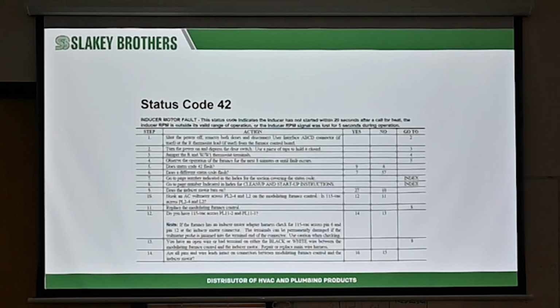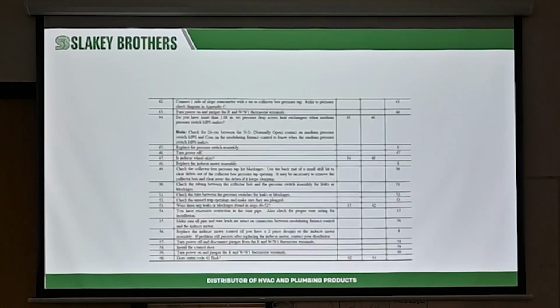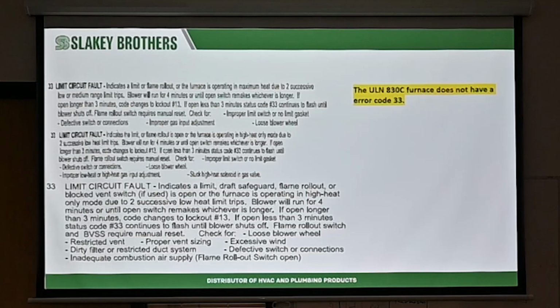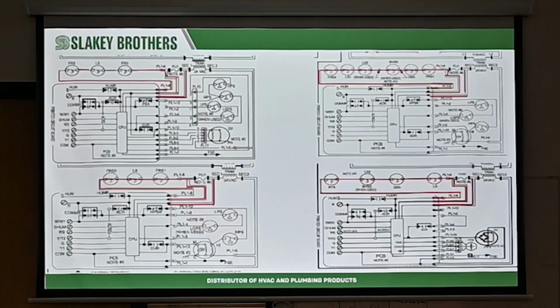All this stuff here, your 42 for your inducer motor, is all in your manual. This is all stuff that I just copied and pasted off of the manuals from where I found it online. Limit circuit faults, simple. The furnace overheated. It should never overheat on any of our units because they're constant airflow. If they're overheated, two-stage or modulating furnace, the first thing to always check is to make sure that the gas pressure is set properly on that unit. Otherwise they generally never ever overheat.